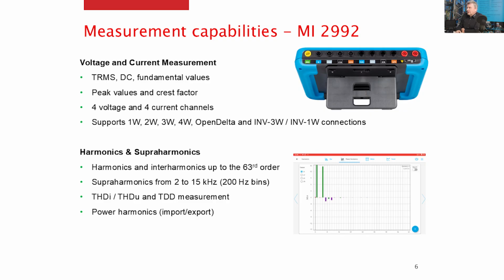Measuring capabilities of 2992. If we focus on the input terminals, the red one is specifically denoted for external supply. Then there are the current inputs and 4 voltage inputs with neutral and ground terminal. We are measuring and analyzing specifically true RMS value, DC and fundamental values, then for each channel, peak and crest factor. We support different types of connections, and also connection for specific photovoltaic inverters or UPS systems, where you connect AC voltage and also DC simultaneously for specific analysis. In this case, DC is presented also with the ripple factor and also the efficiency of the system comparing the AC and DC parts.